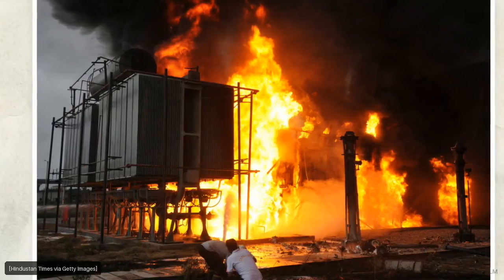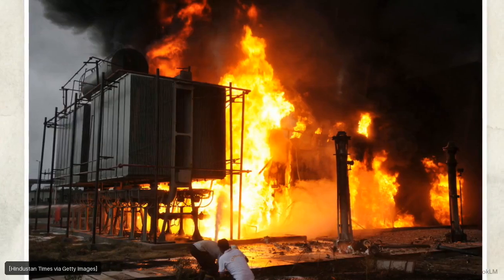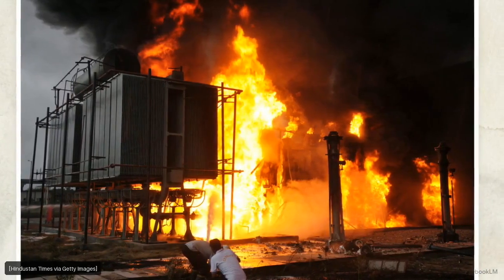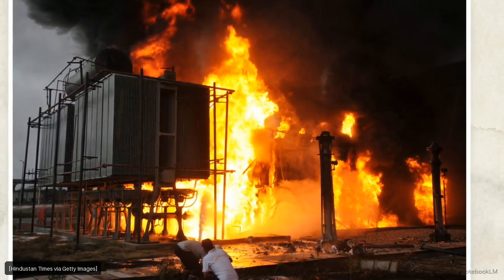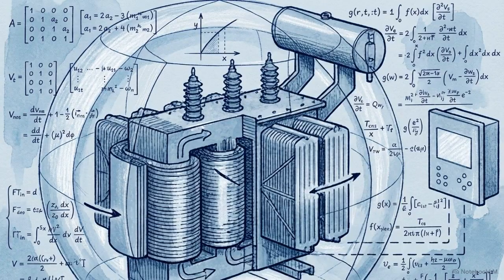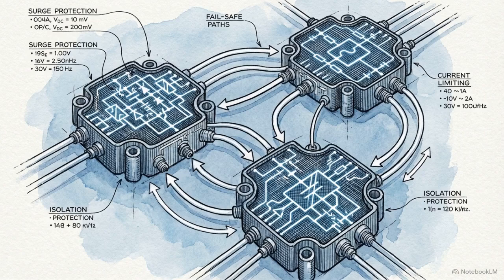Conversely, a failure to trip allows thousands of amps to feed an internal arc, rapidly culminating in a tank rupture and oil fire. Protecting a transformer requires a departure from simple current comparison. Engineers must deploy a sophisticated architecture of mathematical compensation, adaptive restraints, and physical failsafes.